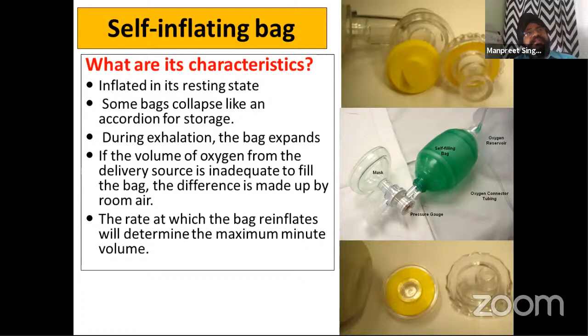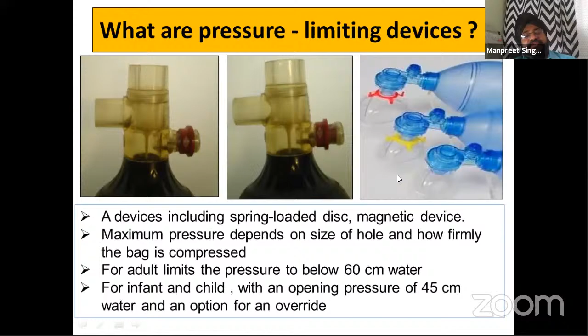What are the pressure limiting devices in this? Sometimes PEEP is also given through this. There are certain extra devices attached, a spring loaded disc and a magnetic device. You can see here, this is the extra one attached, and the maximum pressure depends on the size of the hole and how the bag is compressed. For adults, pressure is maintained at less than 60 centimeters of water, and for infants and children, less than 45 centimeters.